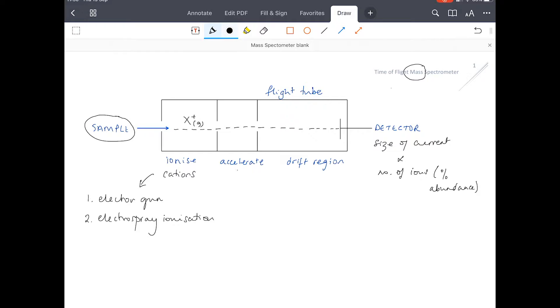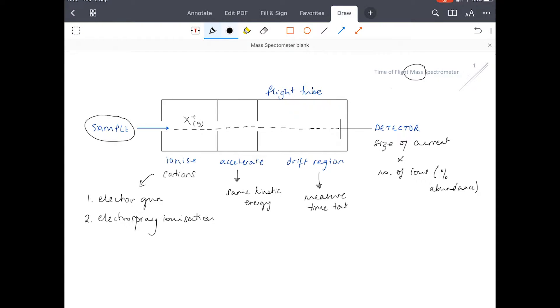Let's go back to stage two. When our ions are accelerated, they are accelerated so that they all have the same kinetic energy. When they move into the drift region, we can time — in stage three here — we can measure the time taken for them to drift through the drift region and hit the detector, so we can measure time taken. Time taken, measured in seconds, to drift from one end of the drift region of the flight tube to the detector.